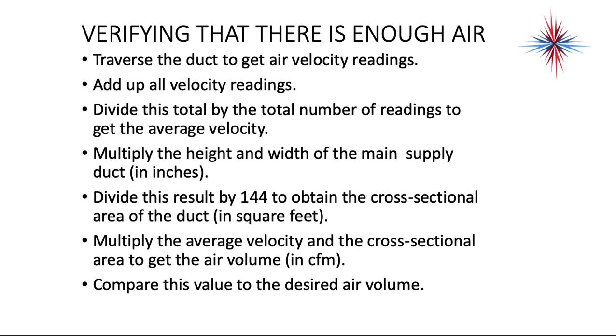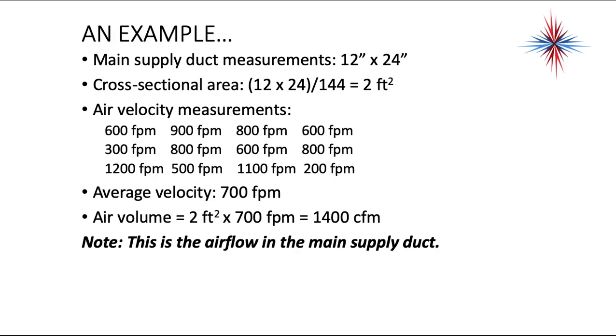To verify there's enough air, you want to traverse the duct to get air velocity readings. Add up all the air velocity readings and divide by the number of readings to get the average velocity. Multiply the height and width of the main supply duct in inches, then divide that result by 144 to obtain the area in square feet. Multiply the average velocity by the cross-sectional area to get the air volume, then compare this to the desired air volume.